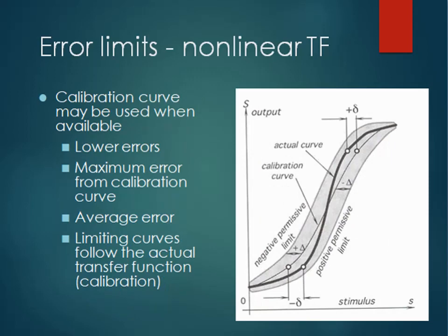Calibration curve may also be used whenever it is available. So it indicates the lower errors, maximum error from the calibration curve, and average error. The limiting curves follow the actual transfer function.